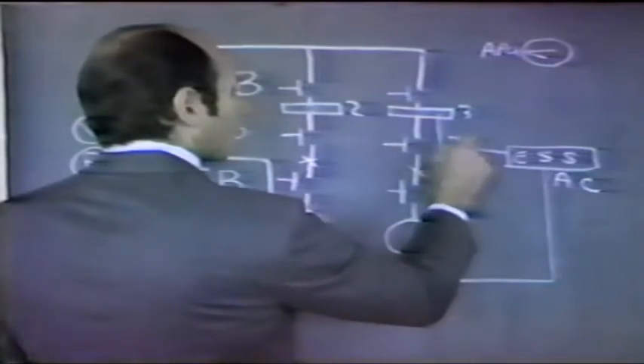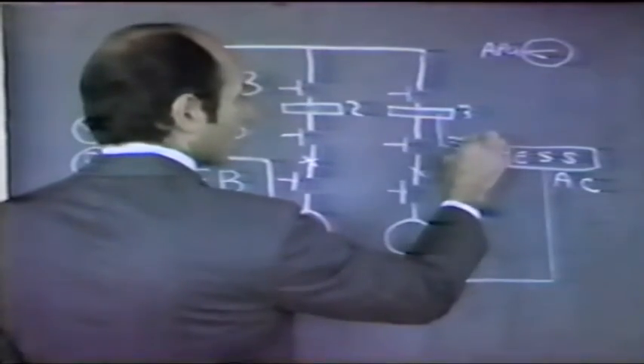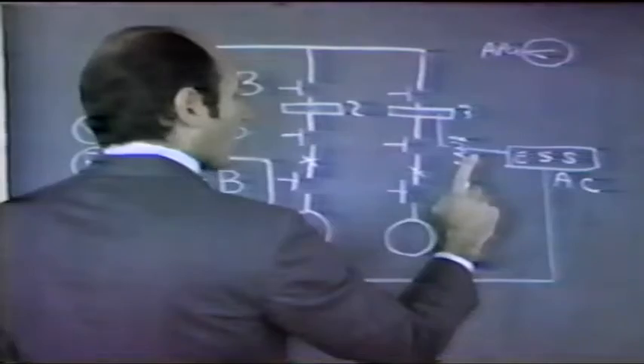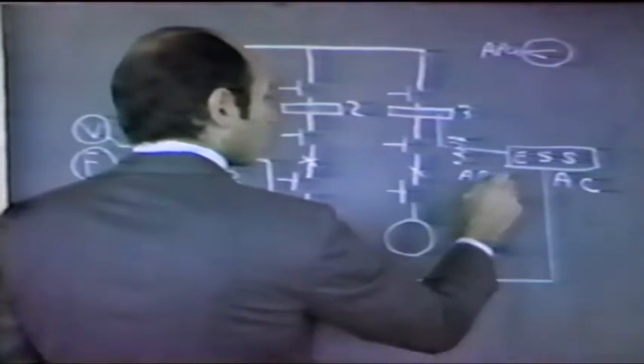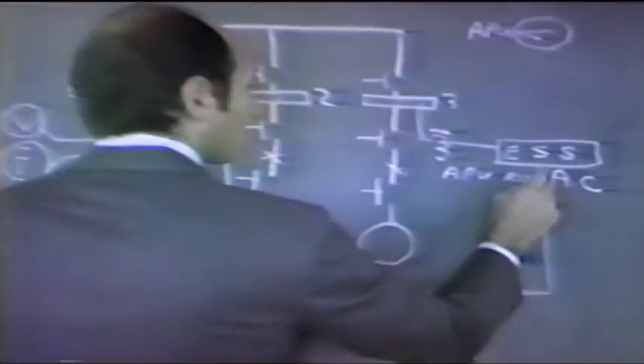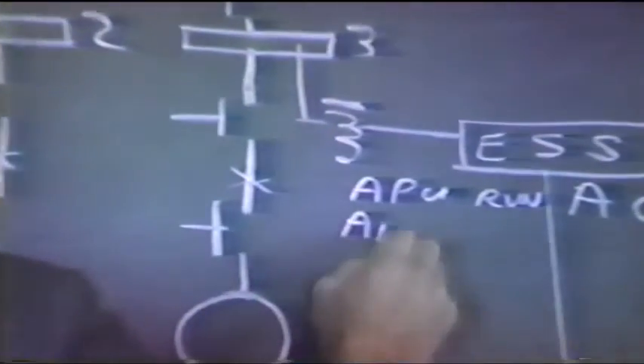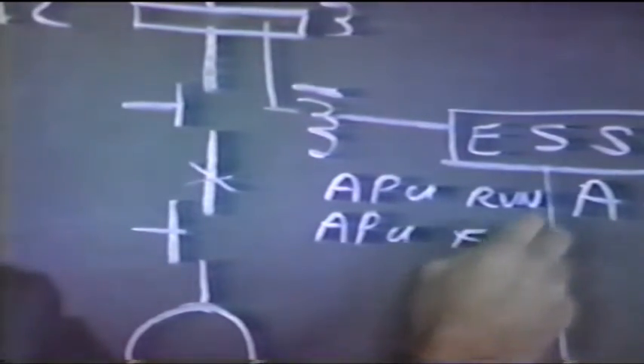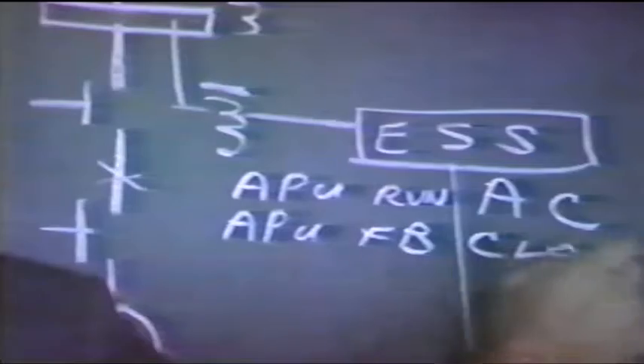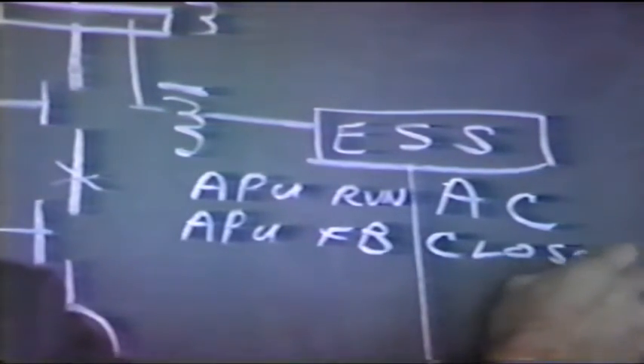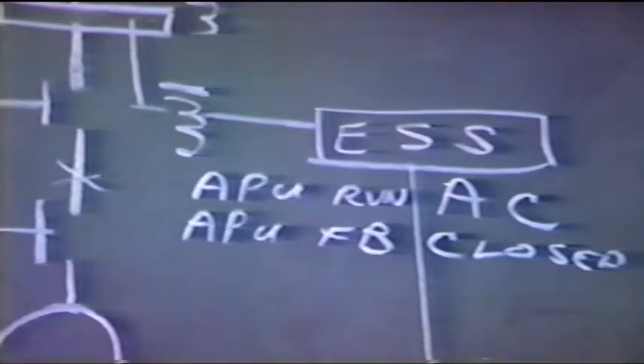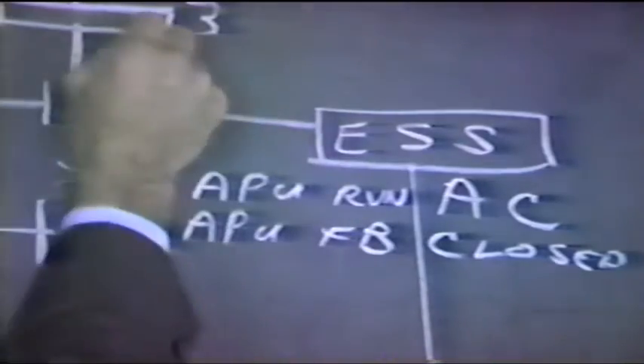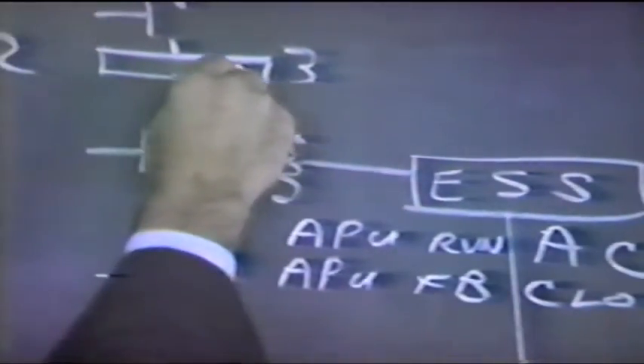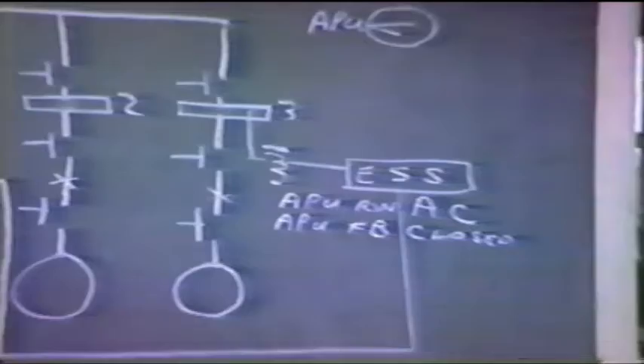We have an interlock here which we must satisfy - we'll call that a relay. We have to have the APU running and the APU field breaker must be closed. Now, if we've satisfied those 2 conditions, then whatever's powering the number 3 bus will power essential power.